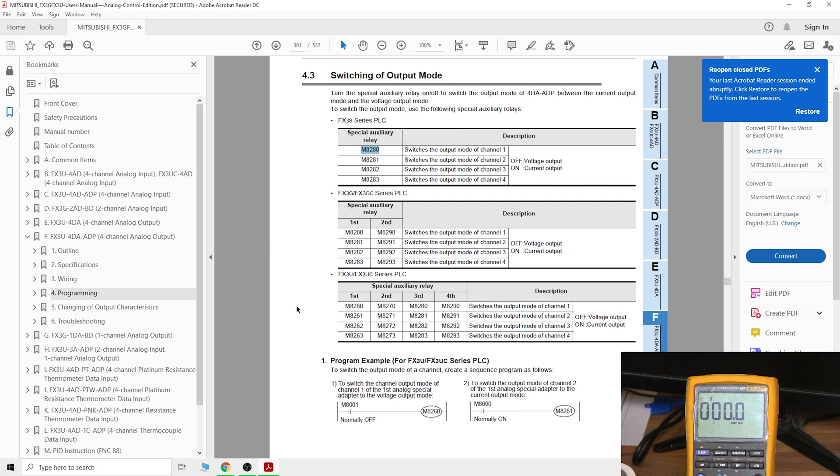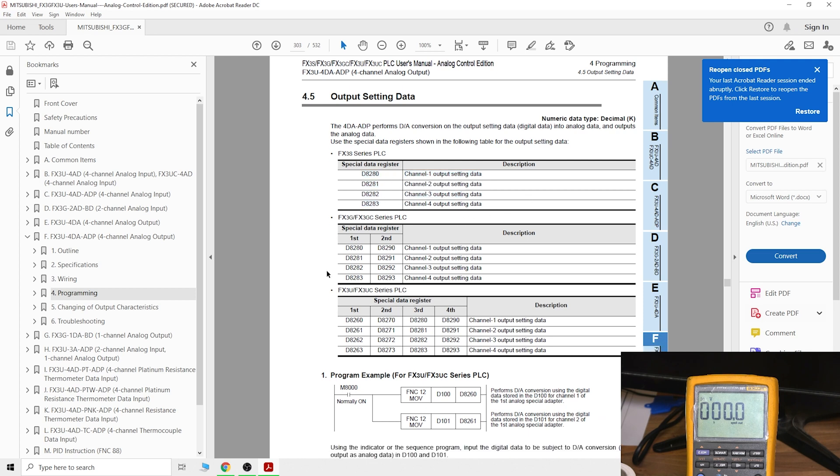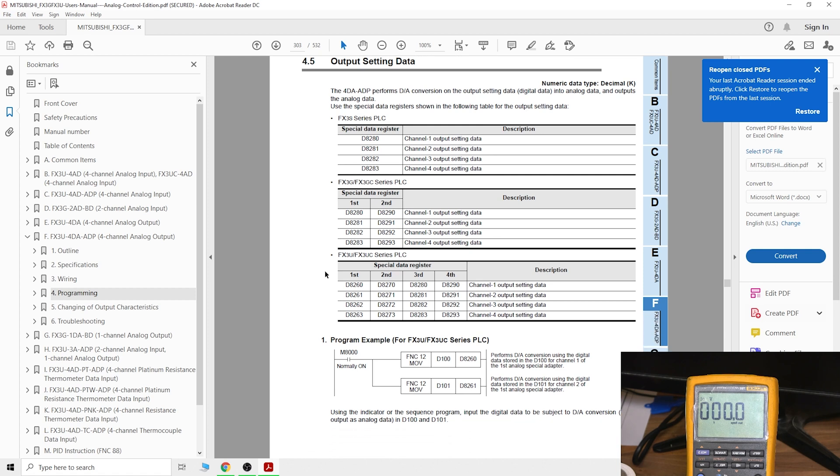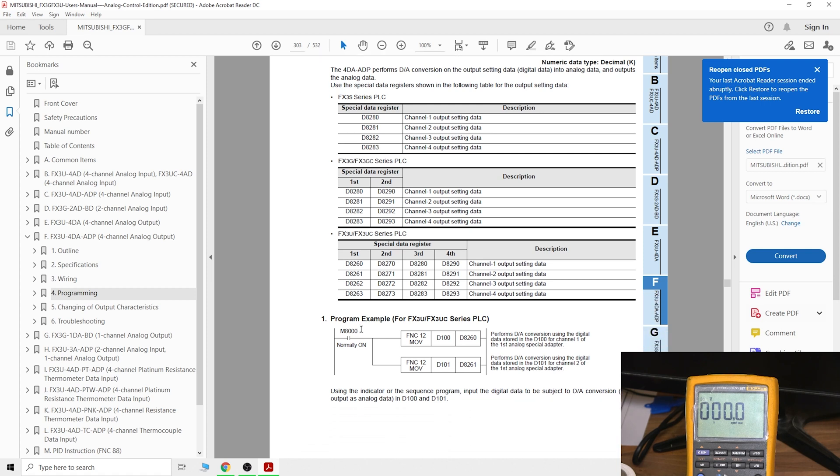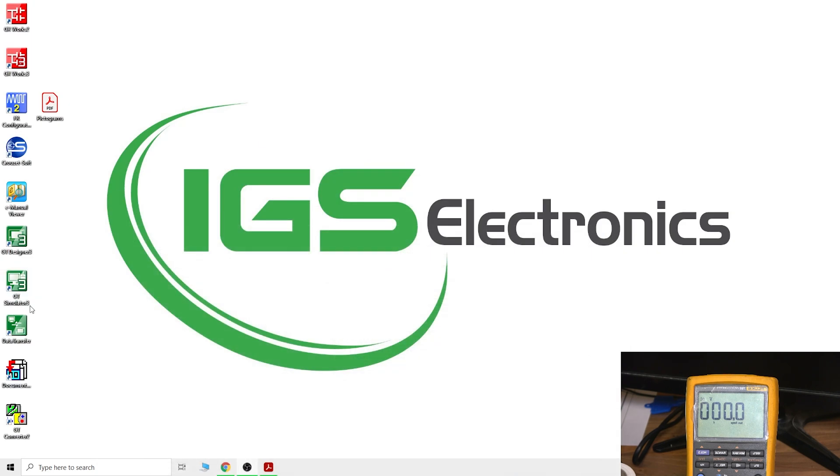You would need some form of FX3G PLC so you can have separate signals. Same signals as for analog input cards for analog output cards. If you are outputting voltage, we don't need to do anything, that stays off. If we are outputting current, we need to turn on one of these. Whichever channel we're using, we need to make sure that M8280 is on. Let's go further and look at the data registers.